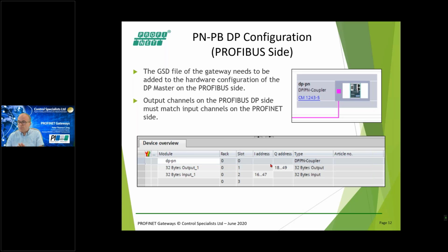So there's no programming of these at all. It is simply you deciding how much data you want to read from the other side and how much data you want to write. It does not have to be the same size at all. That's basically it. Now you think, well, maybe all of them are like this, and generally, yeah, the answer is yes, they are very much like this. It's just a matter of configuring both sides. You may be only responsible for one, it doesn't matter. If you want more data, you just change the modules. Very straightforward.